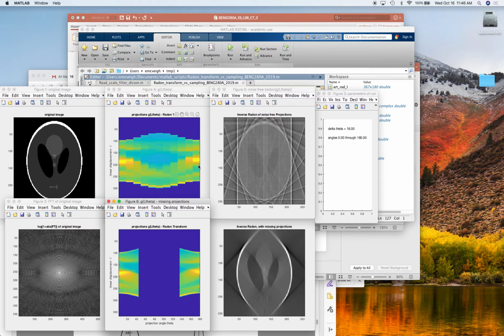A CT scanner, the time resolution is an interesting thing because the gantry is spinning at a certain rate, and so you're stuck with how long it takes to get, say, 180 degrees of views. It's fixed by whatever the rate is. CT scanners often let you change the rotation rate of the gantry. You don't always run it at its highest rotation rate because certain things need greater X-ray fluence, and so you just spend longer at each view getting more X-rays. Okay?